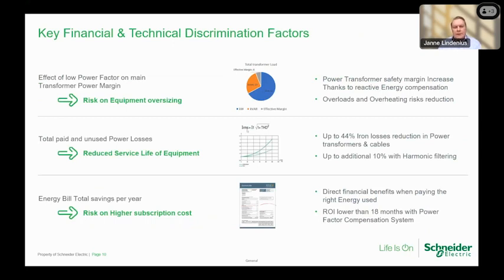There are some key financial and technical discrimination factors to be considered here. Effect of the low power factor on main transformer power margin. That will lead to a risk of equipment oversizing. Power transformer safety margin increased thanks to the reactive energy compensation. Less kVA will go through the transformer, allowing a smaller equipment sizing. Overloads and overheating risk reduction. Reduced current will lead to improved voltage level, reducing the overloading and heating conditions. The total paid and unused power losses cause reduced service life of the equipment. Iron losses reduction in the power transformers and cables. Less current means less losses. Up to an additional 10% with the harmonic filtering. A reduction of the harmonic portion from the system reduces the harmonic effect. Energy bill total savings per year. Risk of higher subscription costs. That's a direct financial benefit when paying for the right energy used. Return of the investment is lower than 18 months with the power factor compensation systems. Next slide, please.